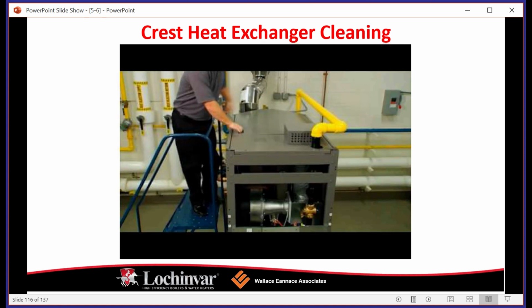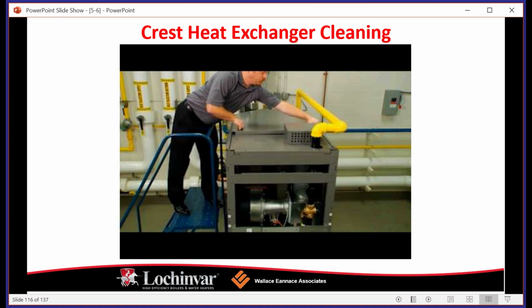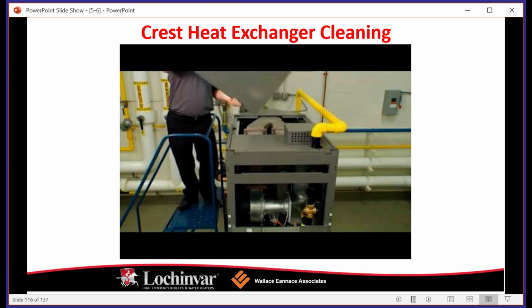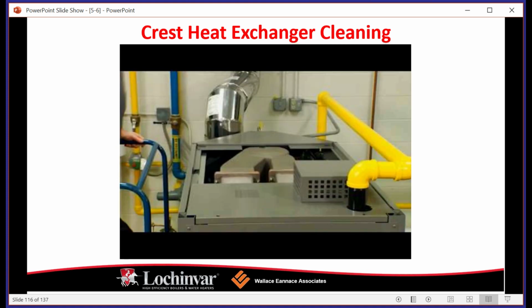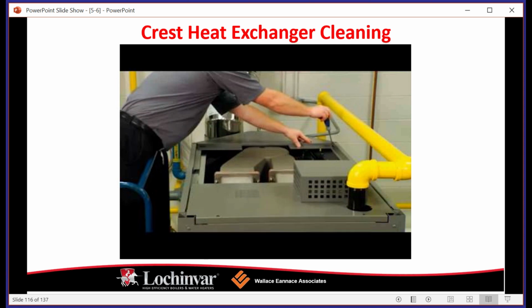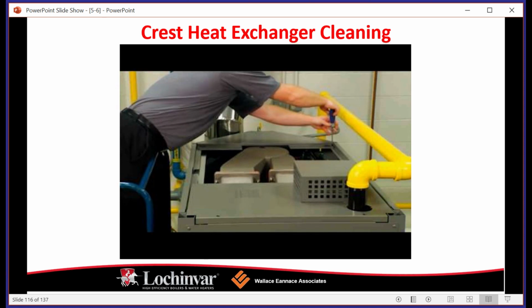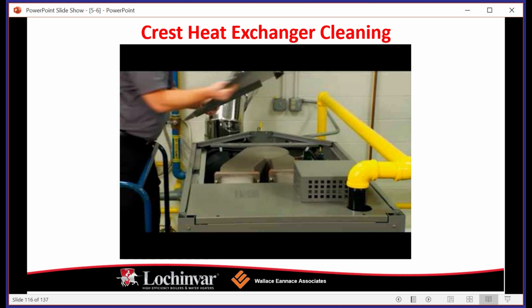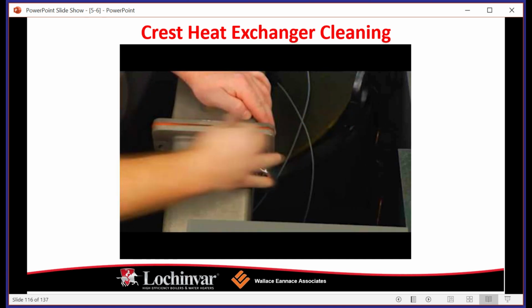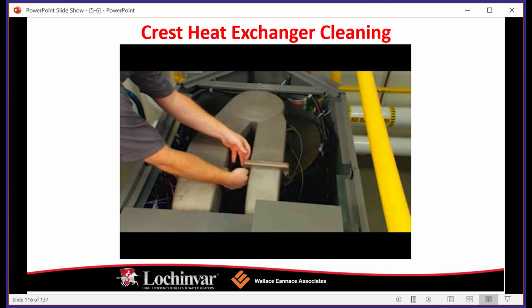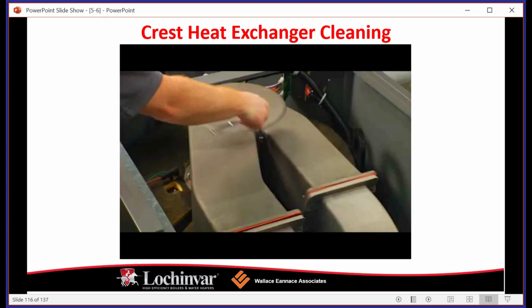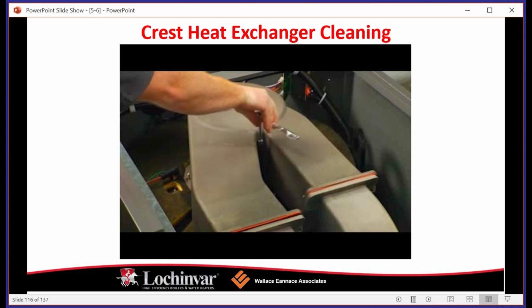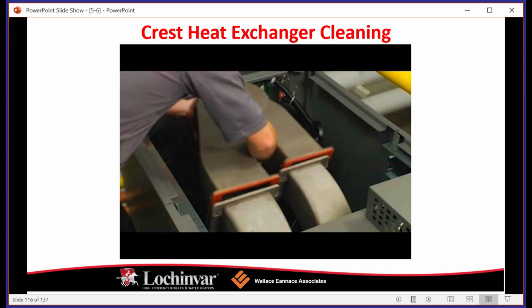Again, you're going to need a meter that's capable of reading microamps, right? Very simple to do. You just disconnect the lead spade connector from the flame connector, and then put one end of your meter on the flame sensor, and the other half onto that connector, and run the boiler, right? So easy enough to do. Clean the heat exchanger if the flue temperature is more than 54 degrees above the return water temperature. Again, that's a really good sign. You're going to see your delta T start to drift. It's not something that you want.